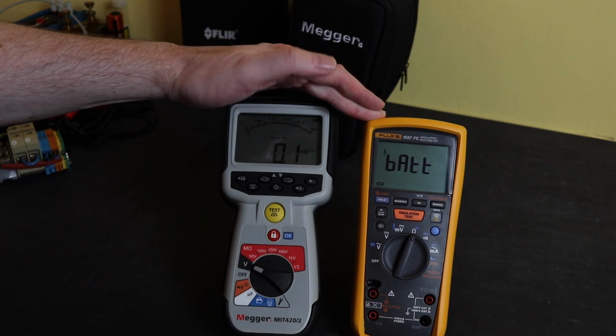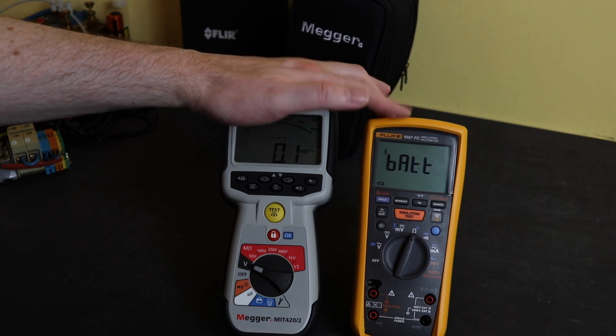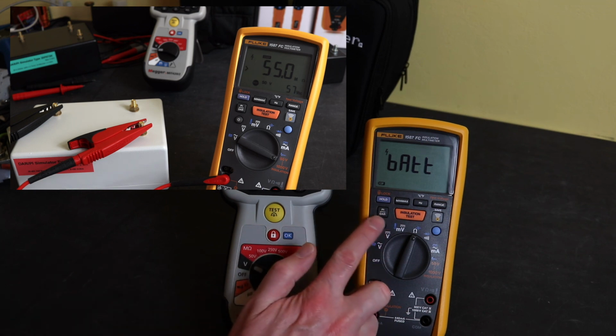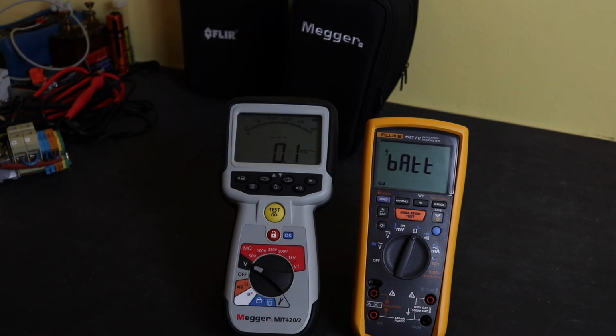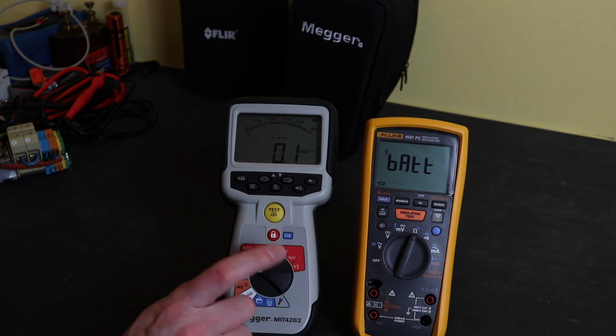With the Fluke, having such a low insulation measurement capability on the 500 volt test, only 550 megohms, quite often this just goes over range, and especially if you're trying to do polarization index tests, quite often you won't get a ratio at all out of the instrument. With the DAR function, even sometimes you'll fail to get a ratio reading. Even if you take the instrument up to 1000 volts test voltage, 2.2 gigaohms just isn't enough for modern day installations, and the IEE and IEC test specs allow you to go up to 5 gigaohms at a 1 minute reading, which obviously the Megger can handle, but the Fluke just can't do that. So that's why, for me personally, I always go for the Megger.